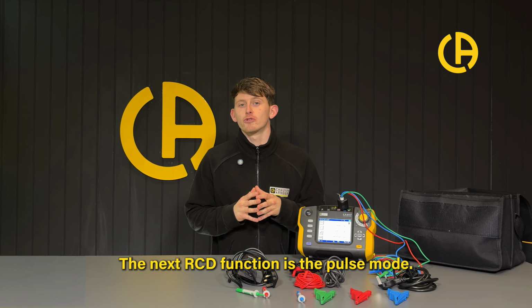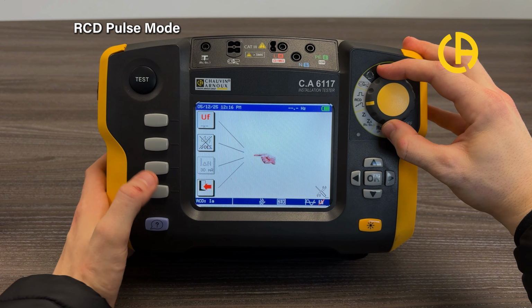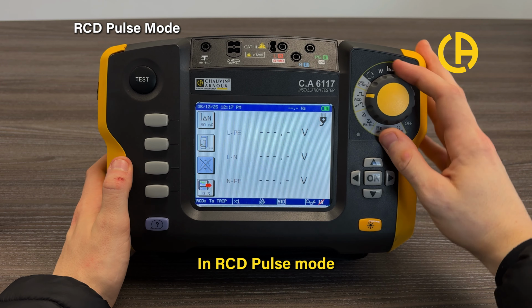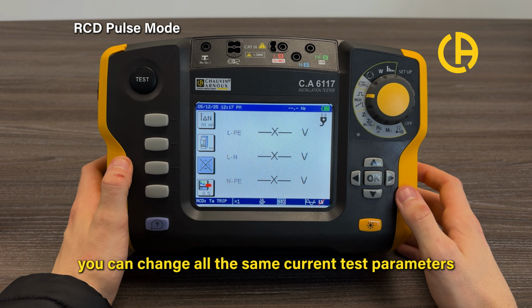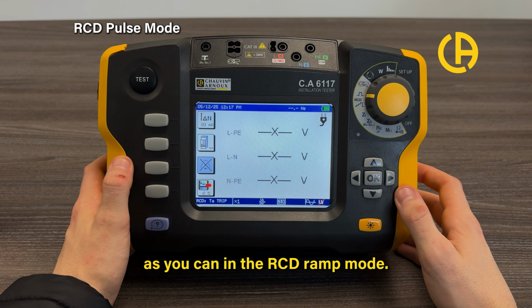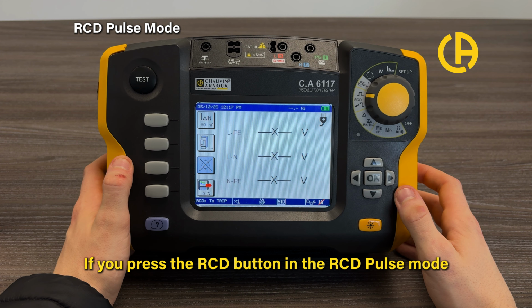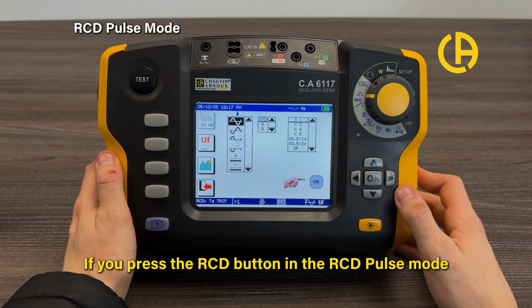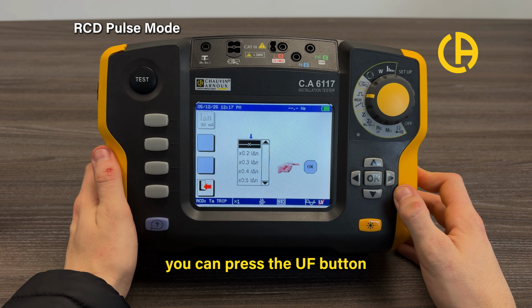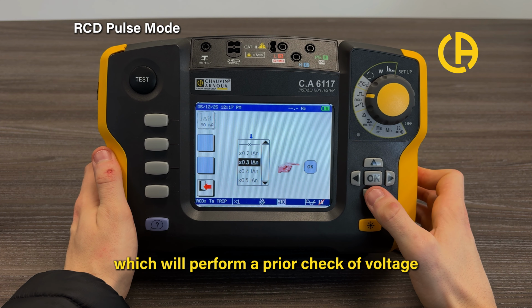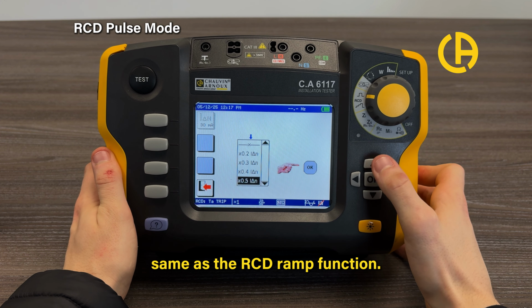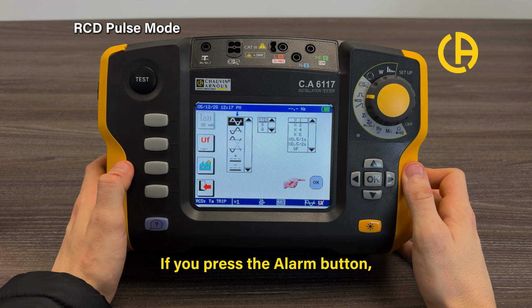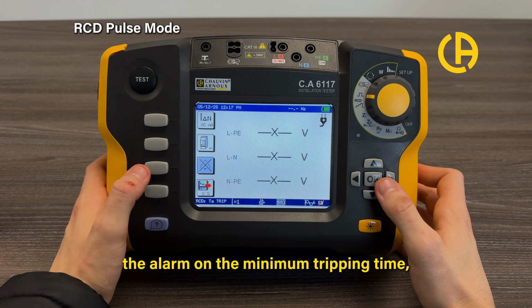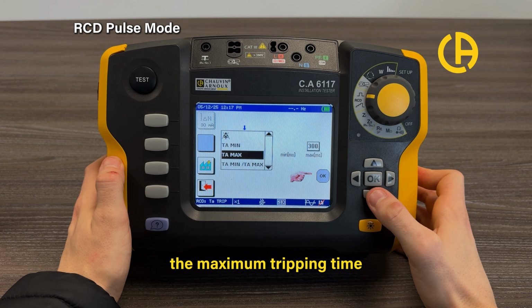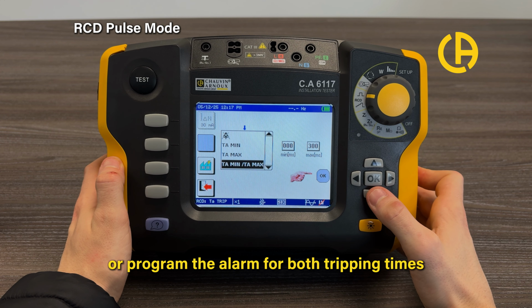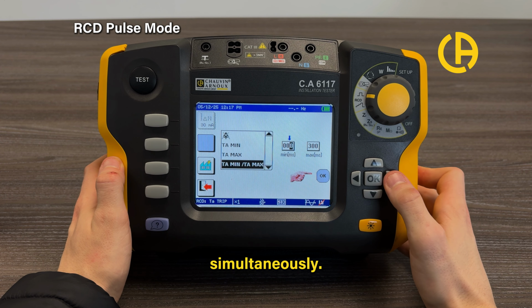The next RCD function is the pulse mode. In RCD pulse mode, you can change all the same current test parameters as you can in the RCD ramp mode. If you press the RCD button in the RCD pulse mode, you can press the UF button, which will perform a prior check of voltage, same as the RCD ramp function. If you press the alarm button, you'll be able to program the alarm on the minimum tripping time, the maximum tripping time, or program the alarm for both tripping times simultaneously.